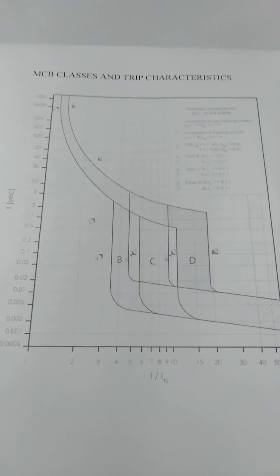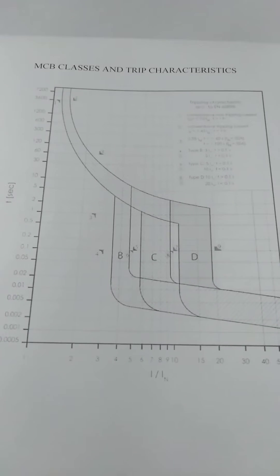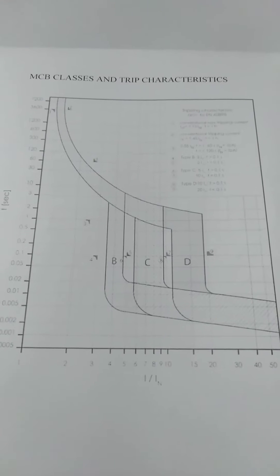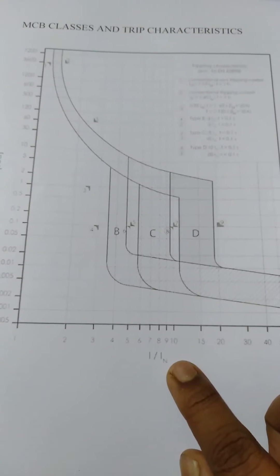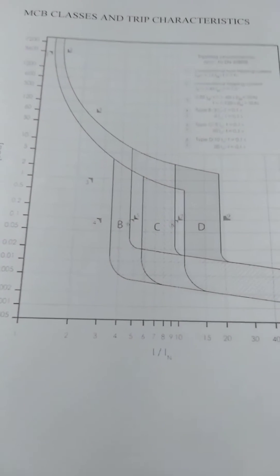As you can see here, the major classes of MCB are B, C, and D. There are other classes such as K and Z, but we don't consider them here. On the X axis, we have current times nominal current, that is the fault current by nominal current, which is the current multiplier. On the Y axis, we have time in seconds, that is the trip time.